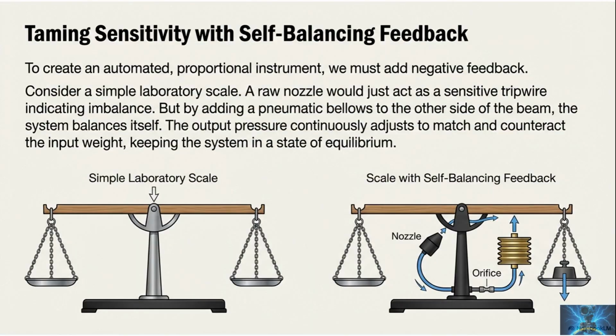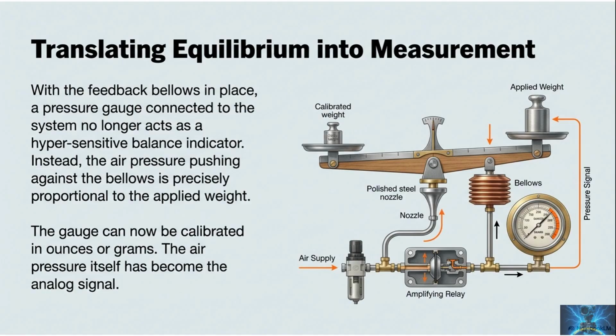Taming sensitivity with self-balancing feedback. To turn a sensitive detector into a proportional instrument, we add negative feedback. Think of a simple balance scale. The nozzle alone would only tell you tilted or not tilted. When you add a pneumatic bellows as feedback, the instrument starts correcting itself automatically. Output pressure pushes on the bellows to counter the input force, driving the mechanism back toward equilibrium. Now the system continuously self-balances instead of wildly overreacting, translating equilibrium into measurement.